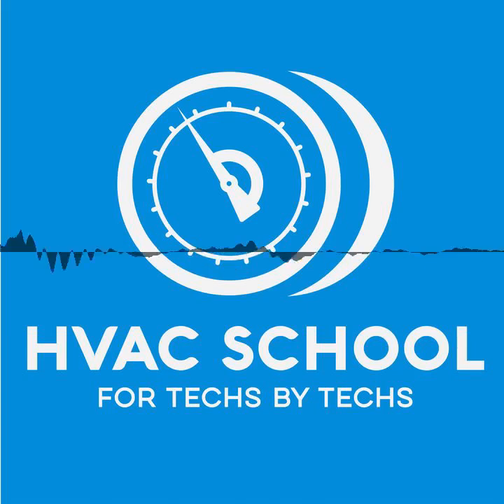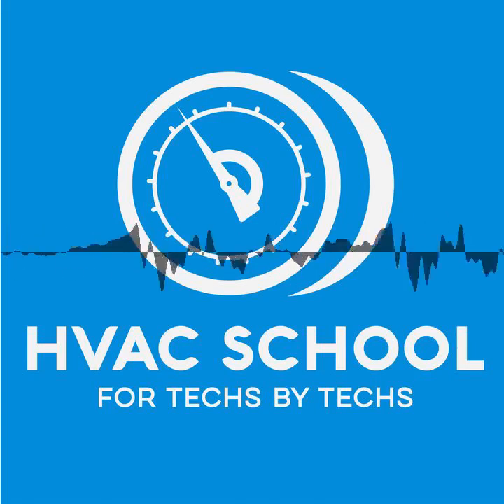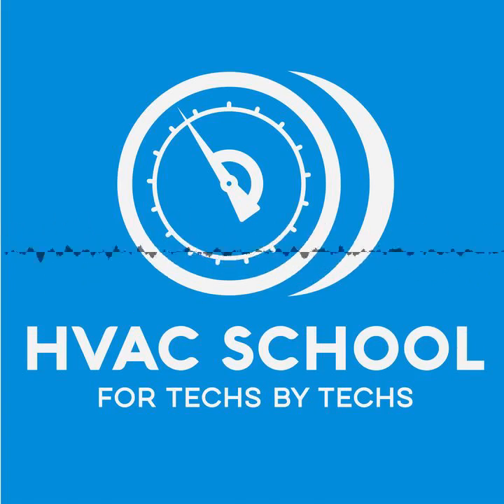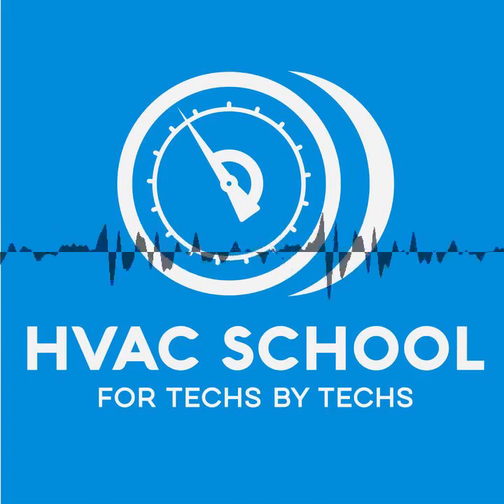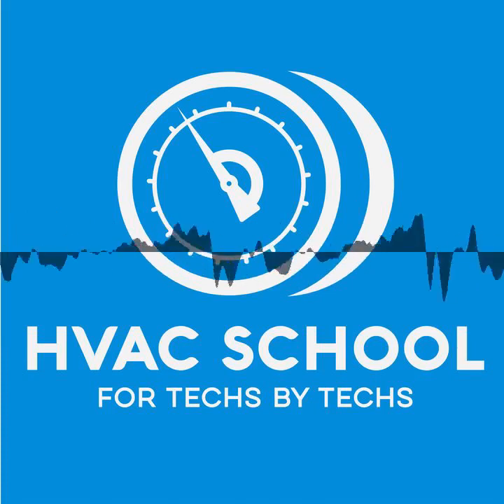Okay. So here's a little science experiment I'd like you to do next time you get a second. Take a tank of 410A or R22, and probably 410A because R22 is so expensive. Put a small amount of refrigerant vapor in your sensor, just like you're purging a hose. Next time you purge a hose, so this can be a de minimis release, purge that refrigerant gas into your vacuum gauge sensor, just the vapor itself. And you're going to see your vacuum gauge is going to drop down to 300, 600 microns. Why the heck is that?